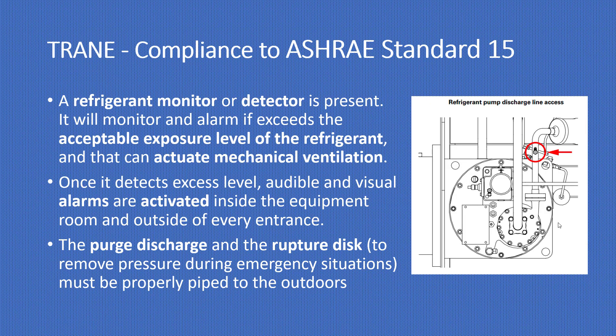Trane complies with ASHRAE Standard 15. A refrigerant monitor or detector is present — it will monitor and alarm if the acceptable exposure level of refrigerant is exceeded, and can activate mechanical ventilation. Once an excess level is detected, audible and visible alarms are activated inside the equipment room and outside every entrance. The purge discharge and the rupture disc must be properly piped to the outdoors to relieve pressure during an emergency situation — you can see this in your plant room. This compliance is always fulfilled.